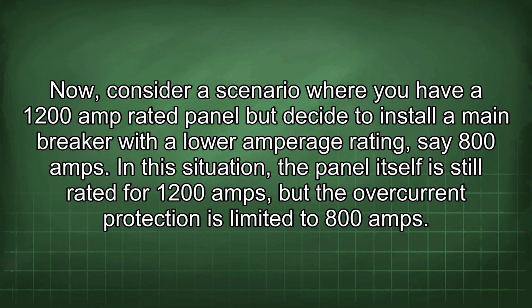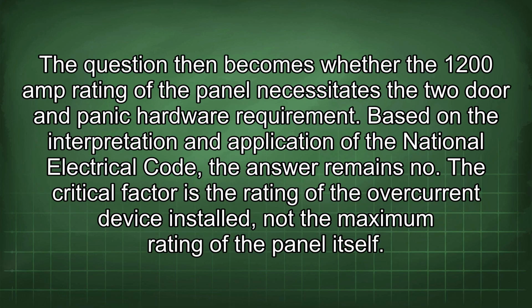In this situation, the panel itself is still rated for 1200 amps, but the overcurrent protection is limited to 800 amps. The question then becomes whether the 1200 amp rating of the panel necessitates the two-door and panic hardware requirement. Based on the interpretation and application of the National Electrical Code, the answer remains no.